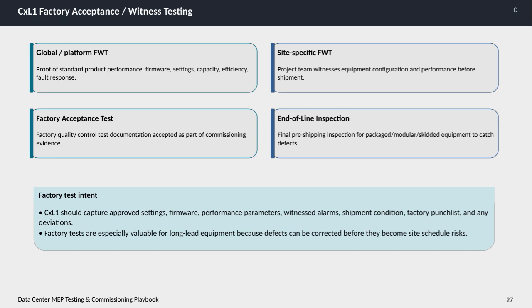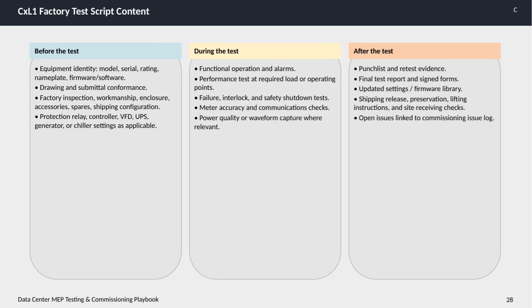risks down the line. Before starting the test, it's crucial to verify the equipment identity, including the model, serial number, rating, nameplate details, and firmware or software versions. We also need to ensure that everything conforms to the approved drawings and submittals. A thorough factory inspection should be conducted to check workmanship, enclosure condition, any accessories or spares, and the shipping configuration. Additionally, settings for protection relays, controllers, VFDs, UPS units, generators, or chillers should be reviewed as applicable.